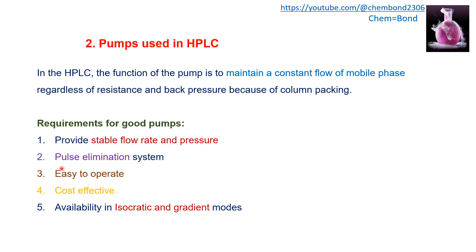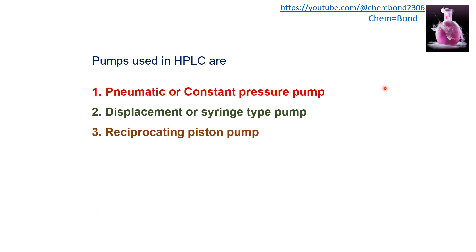Requirements for good pumps include: providing a stable flow rate and pressure pulse elimination system, easy to operate, cost effective, and available for isocratic and gradient modes of elution. Pumps used in HPLC are: pneumatic or constant pressure pump, displacement or syringe type pump, and reciprocating piston pump.